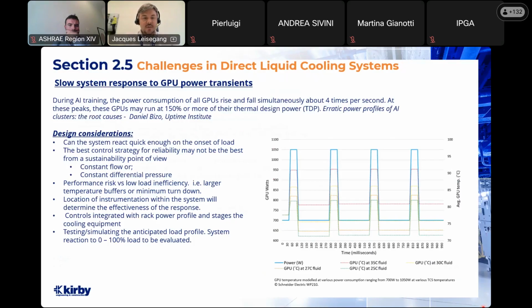The best control strategy for reliability may not be the best from a sustainability point of view. Are we going with a constant flow or constant differential pressure? We've seen both solutions being spoken about in the initial designs that we've seen. So understanding what that load profile is is a big part in how we design the control system. We have to trade off a performance risk versus the low load efficiency. Are larger temperature buffers or minimum turn down preferred?